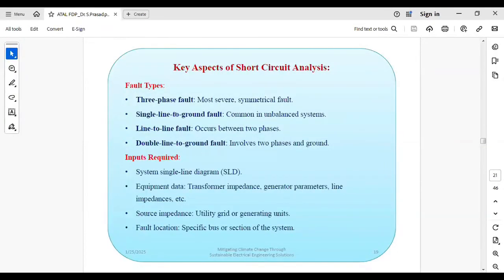There are different types of faults: the three-phase fault, which is more severe, and the single line to ground fault, line to line fault, and double line to ground fault. What are the inputs required for this study? The single line diagram of the system, a PV plant single line diagram when it is connected to the grid. Then equipment data, for the various types of equipment used in a PV plant: transformer impedance, generator parameters, line impedance, etc. And source impedance, of the utility grid or generating unit.